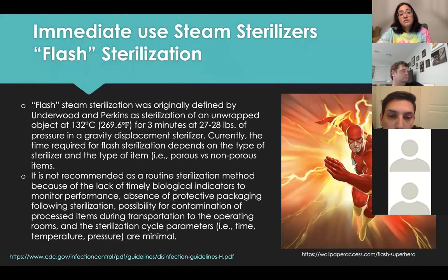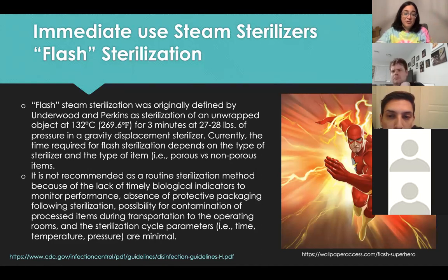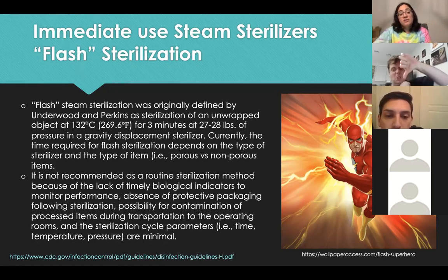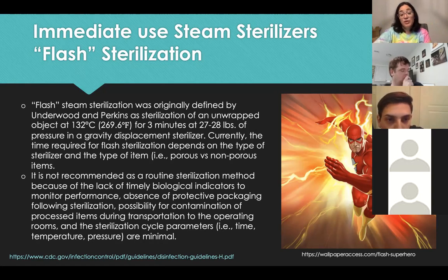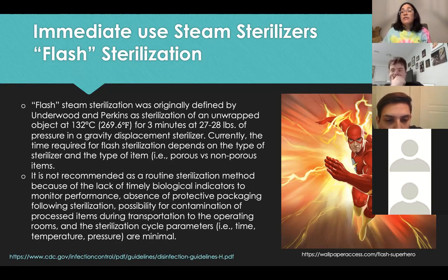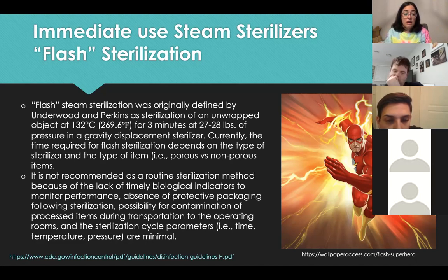IUSS — immediate use steam sterilization — was formerly called 'flash' sterilization, which is a somewhat outdated term. Flash steam sterilization was originally defined by Underwood and Perkins as sterilization of an unwrapped object at 269.6°F for three minutes at 27 to 28 pounds. IUSS is not recommended as a routine sterilization method. It should only be used in truly emergent situations — when it's a one-of-a-kind instrument, there is absolutely no other way to reprocess it, and it is urgently needed mid-procedure with no backup available.